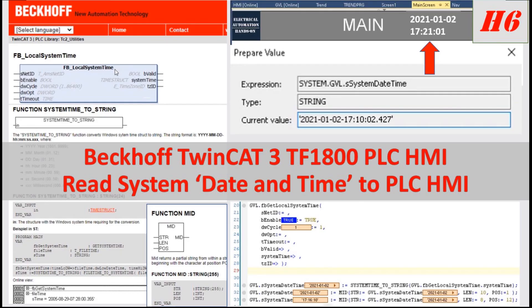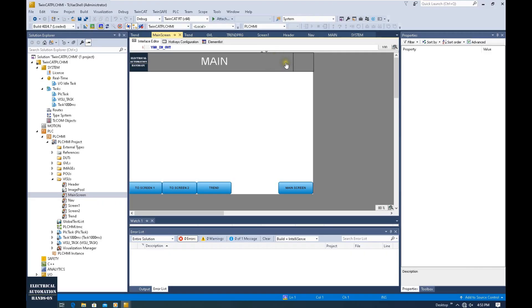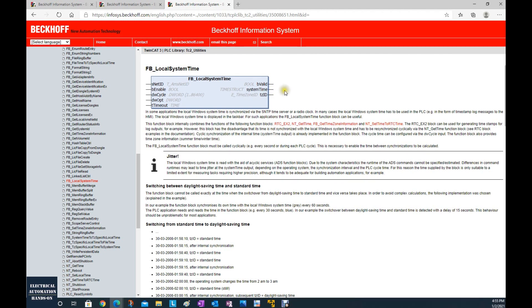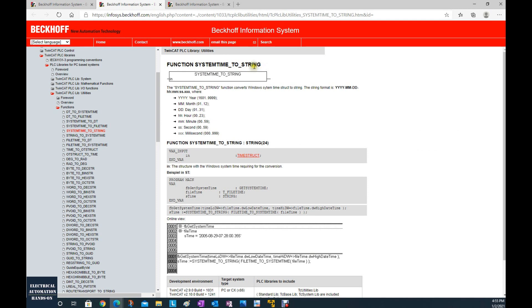In this video, I would like to introduce how to read the system time and date and show it on the main screen of the HMI. We will put the date and time in the header area. To read the system date and time, we need a couple of important function blocks. The first is FB_LocalSystemTime, which comes from the TC2 Utilities library. This function block allows us to read the system time from our controller. To transfer the time structure to a string and show it on the HMI, we need to use the function SystemTime_To_String.